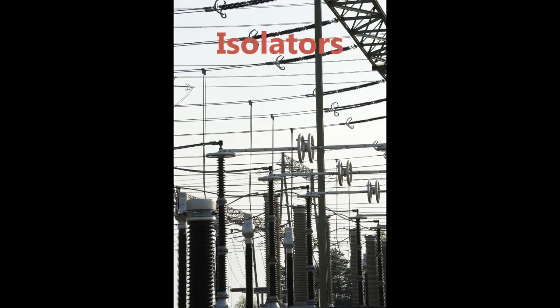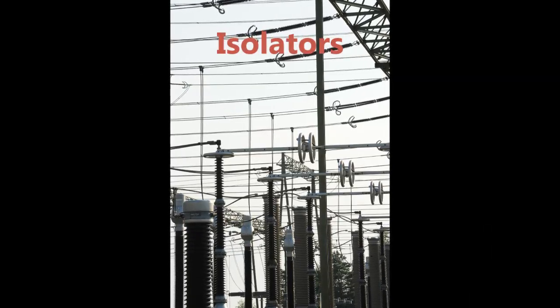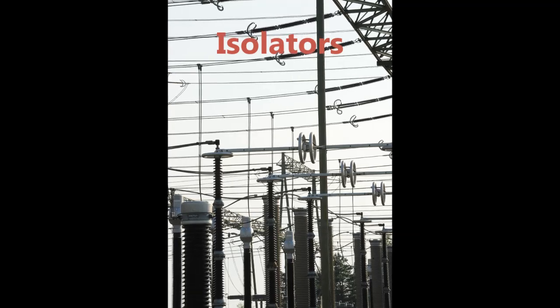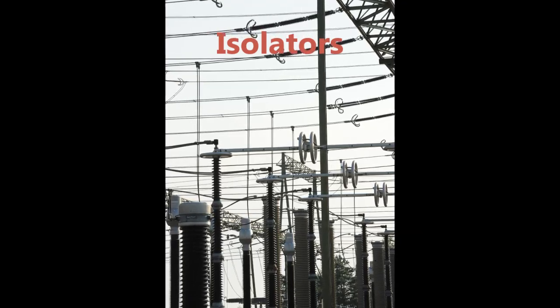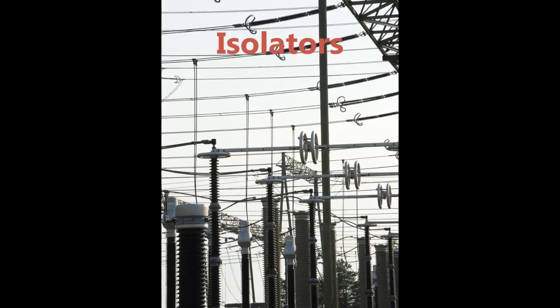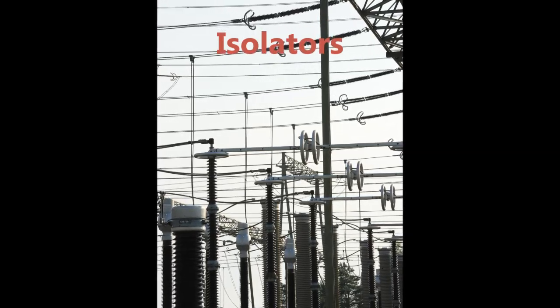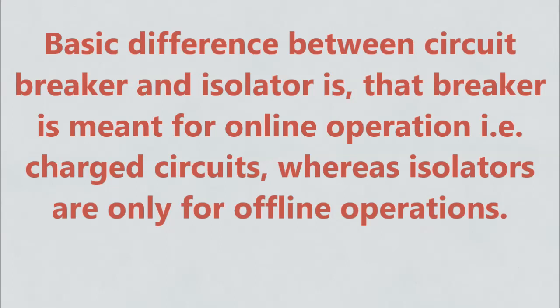Fifth, isolators. These are generally located next to the circuit breaker. The function of an isolator is to isolate the required part of the system — that is, to separate the faulty part from the healthy one — and also to carry out maintenance work. The basic difference between a circuit breaker and an isolator is that a breaker is meant for online operation on charged circuits, whereas isolators are only for offline operations.